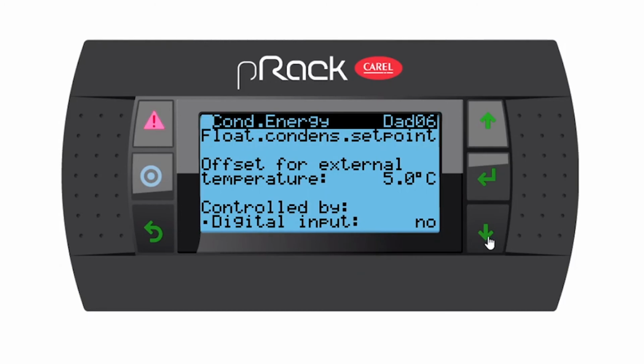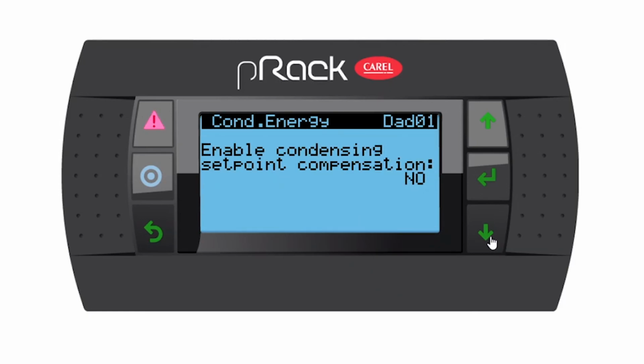Controlled by digital input, no. So I don't want someone to go and actually switch it on with the input. I'm going to let it run all automatically. If you go down, enable condensing set point compensation. Oh, then we're back at the beginning.